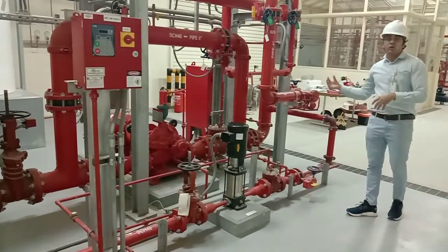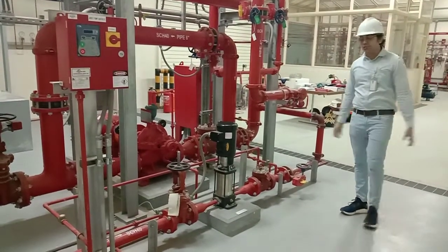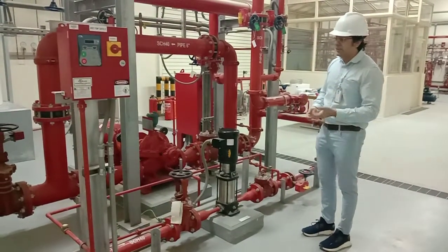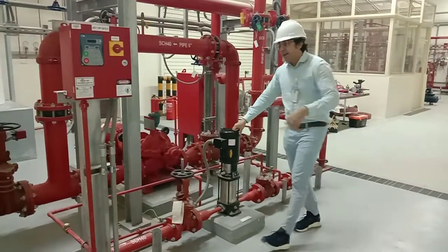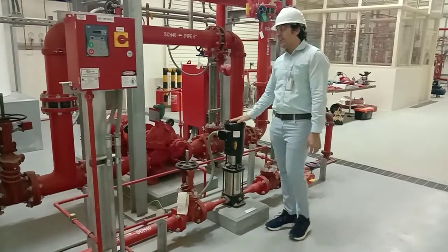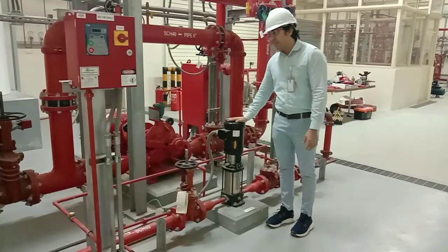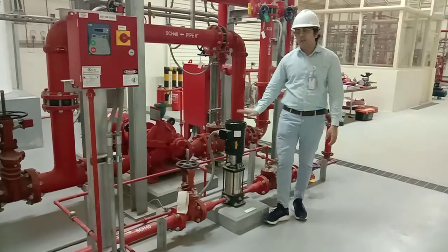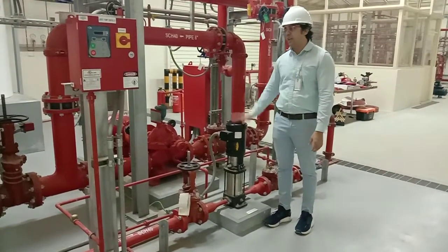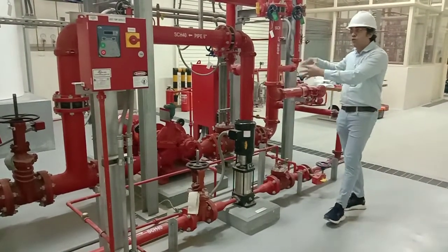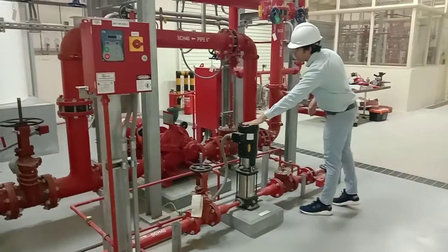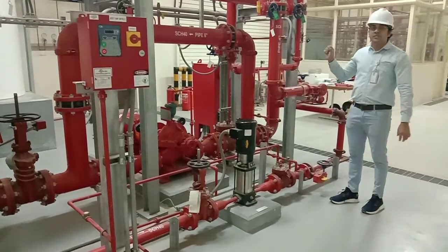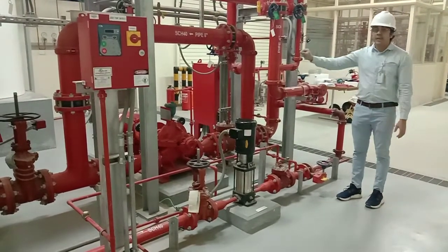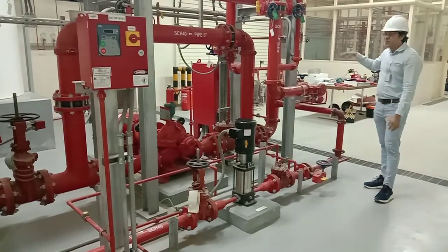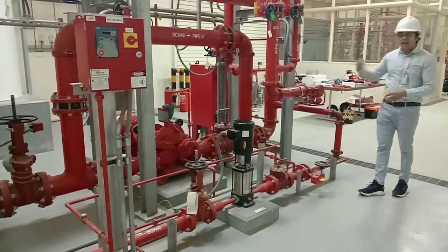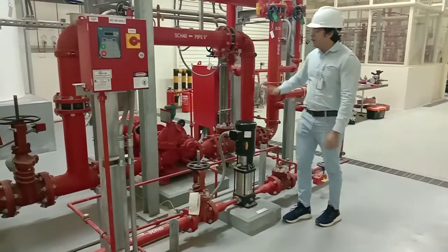But if there is an actual fire and the sprinkler is activated and we need a large capacity of water, let's say around 400 GPM or 500 GPM, the jockey pump will only maintain up to 10 psi. So let's say the jockey pump is rated for 150 psi and the fire pump is rated for 140 psi. This will maintain only a 10 psi higher pressure than the fire pump, right? But if there is an actual fire, there is high flow, and when the flow goes higher, the pressure will reduce. At that time, even though the jockey pump is working, it is not maintaining the pressure. At a 15 psi drop in the main fire protection system line, the main fire pump will start and supply water to the fire protection system. Keep in mind this is the actual fire, and now it will protect our occupancies. Now that is all about the jockey pump.